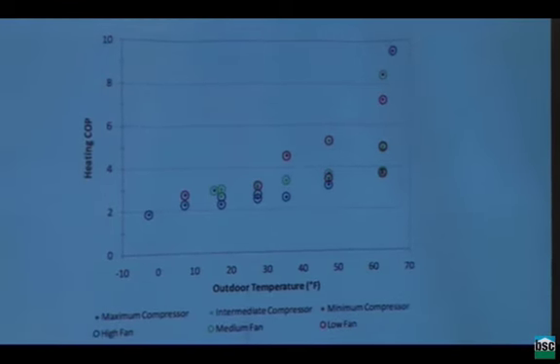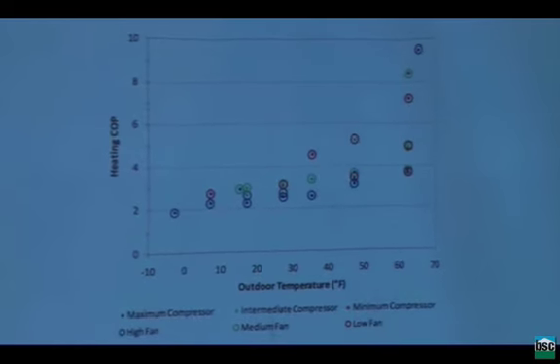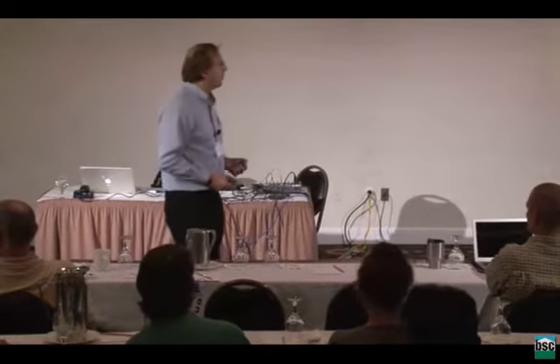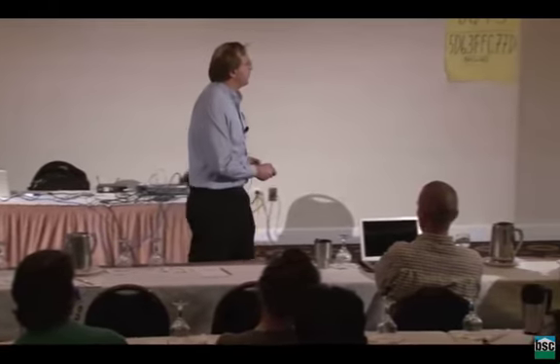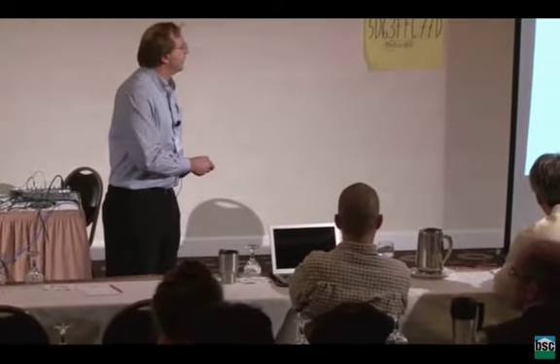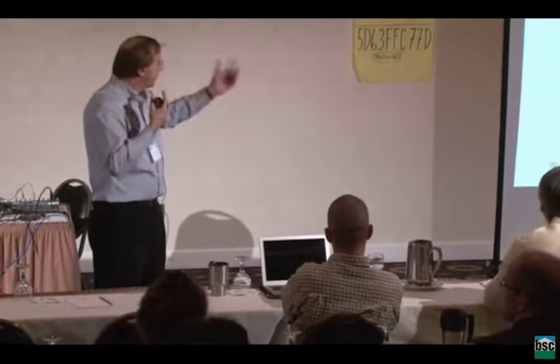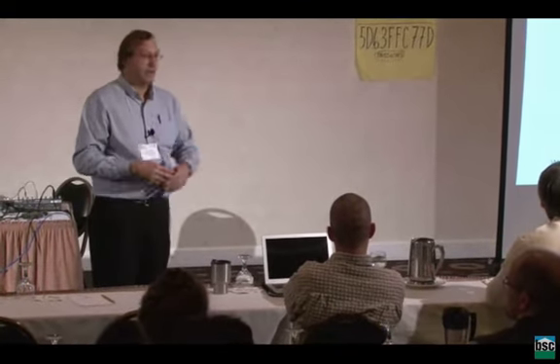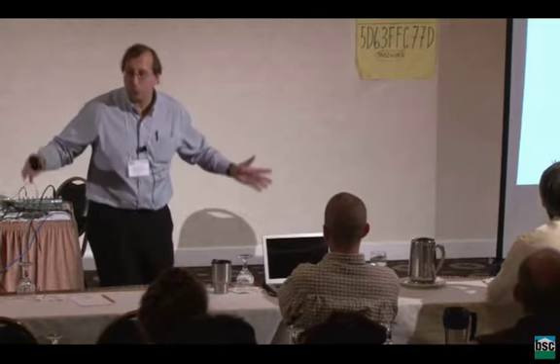So even in places like Seattle, which is not that cold, it's tempting to consider products like this because the COPs can be actually pretty high. And even as you get colder, the COPs under most hours of heating are going to be in the pushing 3 range, and occasionally they will definitely drop to 2 in the 100 hours when it's really cold or it's defrosting or something like that.